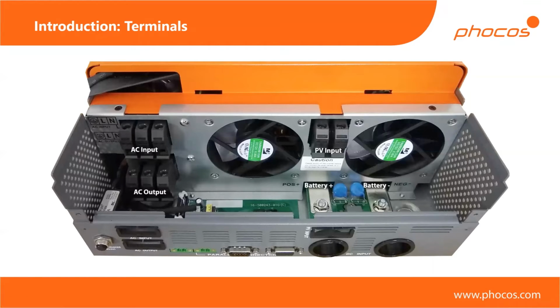Another question coming in: are all the MPPT charge controllers from the inverters individual, or are they hooked up to each other? If you use more than one AnyGrid unit, then each one will handle its own PV array. So basically, if you're multiplying the number of devices, you're also multiplying the number of MPPTs.